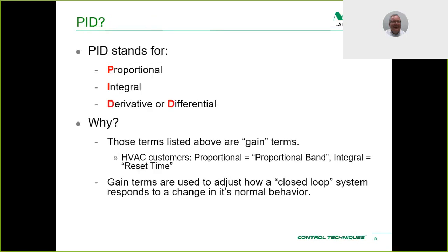And to begin with, PID stands for proportional, integral, and derivative, or differential is sometimes used as well. The terms listed above are gain terms. And I should also point out that for our HVAC customers, sometimes they use different terminology when compared to industrial folks. So the HVAC customers understand that when I'm discussing proportional, that is what you might refer to as proportional band. And when I'm discussing integral term, that's what you might call reset time. So those two things go hand in hand.